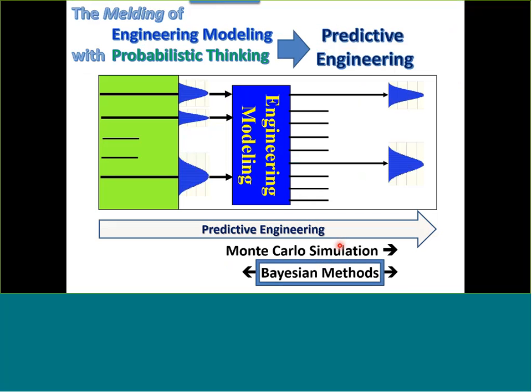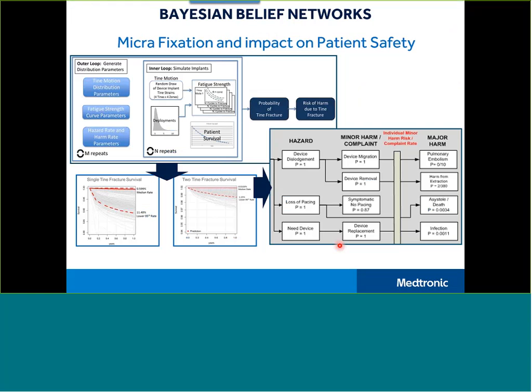Similarly, we did some things on the Bayesian side. So we didn't stop with the Micra fixation, just making sure it was good enough. We also wanted to make sure there was very low probability of major harm. So we built a Bayesian belief network with an outer loop and an inner loop of things that would stress those tines and cause things like single-tine fractures and two-tine fractures and things like that. And we looked at the risk of harm to the patient, minor harms and major harms.